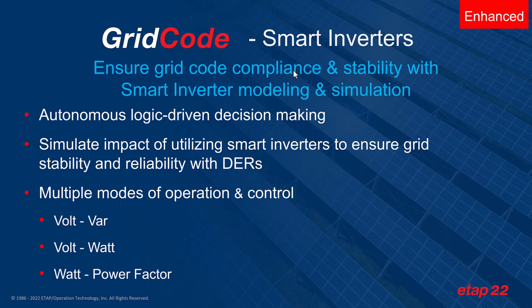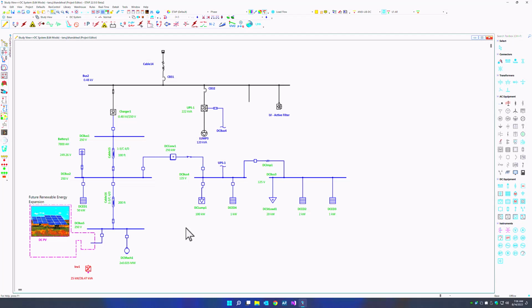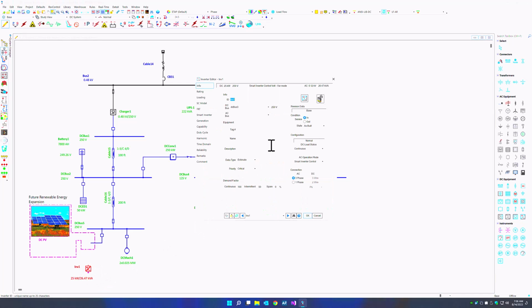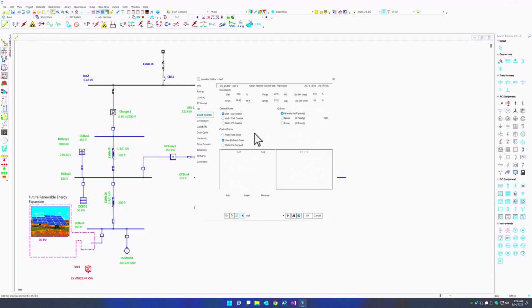Let's take a look at the smart inverter in ETAP 22. We can bring up the inverter property editor and switch the AC operation from any other control mode to smart inverter control. And once we are in the smart inverter control mode, you can specify the constraints of the smart inverter, including the cutoff voltages, specify the control modes, and for these particular control modes, you can also specify the Q or P base, including their priorities.